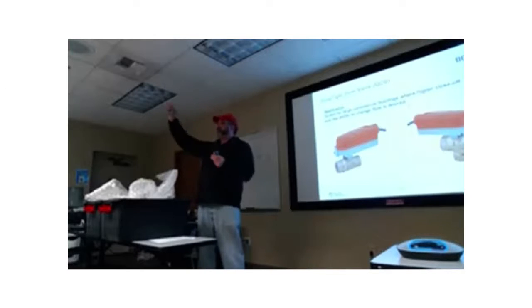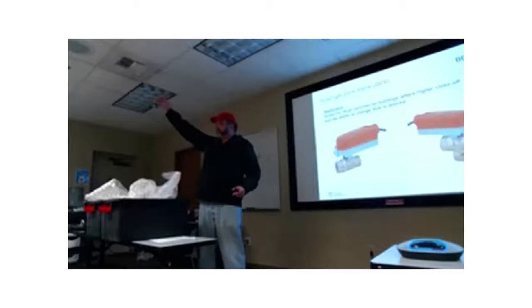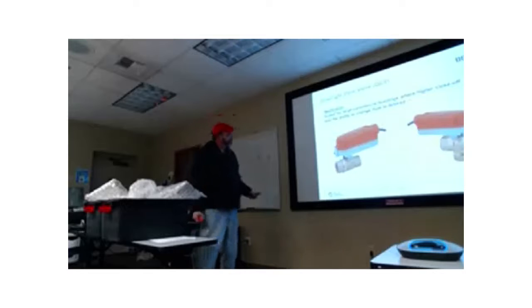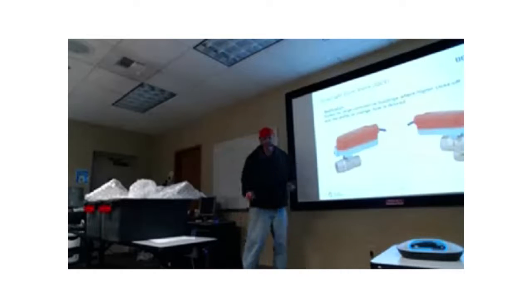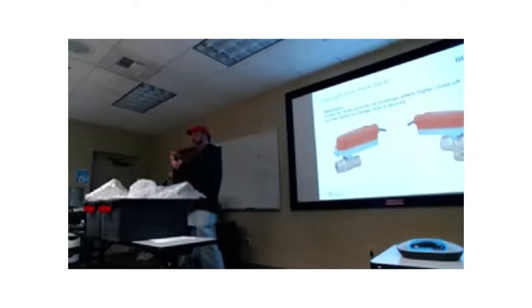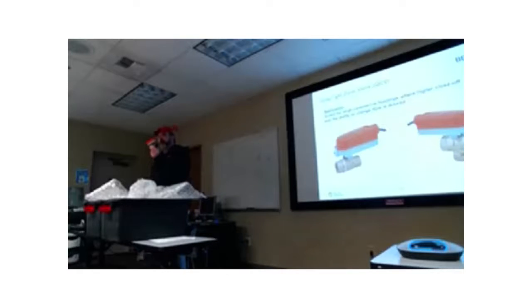So I don't know if you guys have an appreciation for what this is. Look at the size of that thing. That's a 1/2 inch, what we call zone type. This was actually developed a couple years ago. We released it about 2 years ago. You know those radiators on the perimeter of the buildings, right? You've got these little tiny spaces that they go in, and you can't fit normal control valves in. This thing will probably fit in a lot of good spaces.